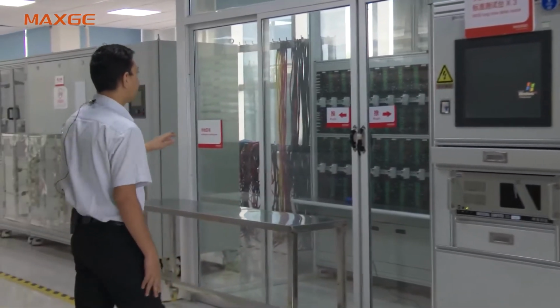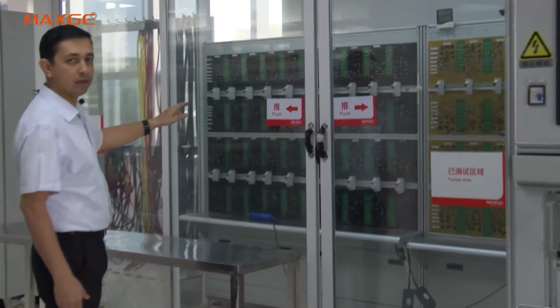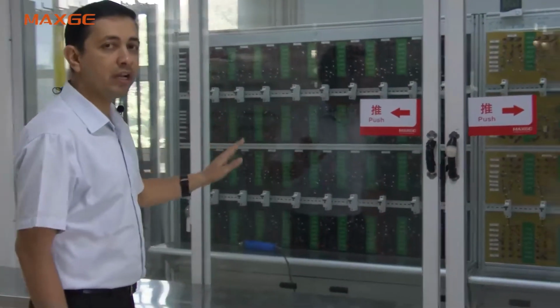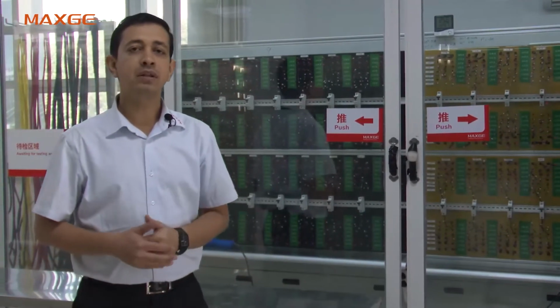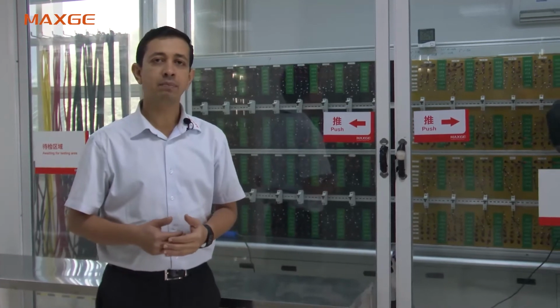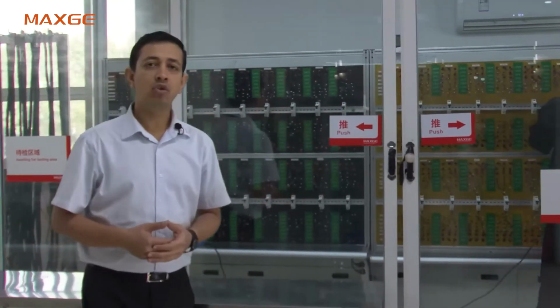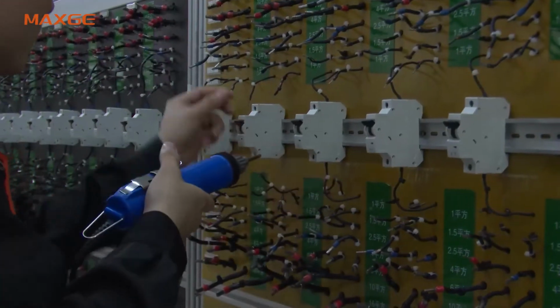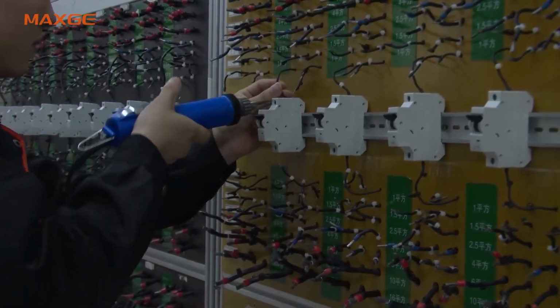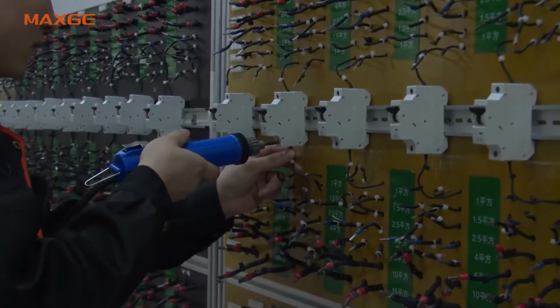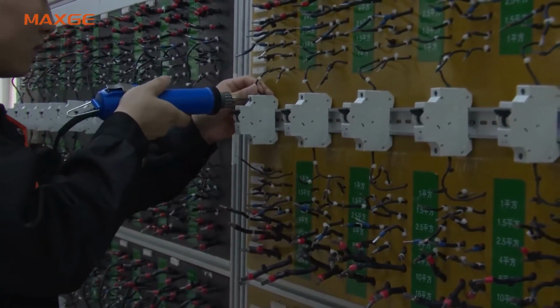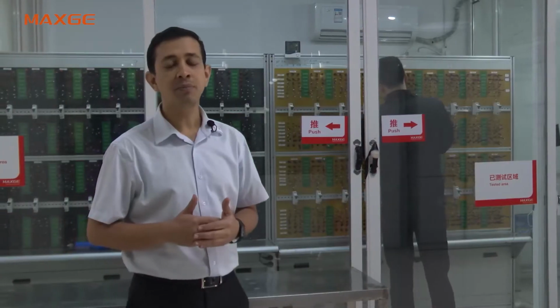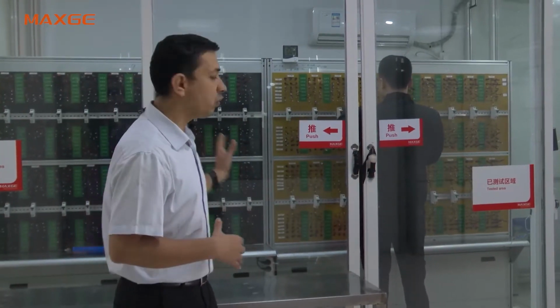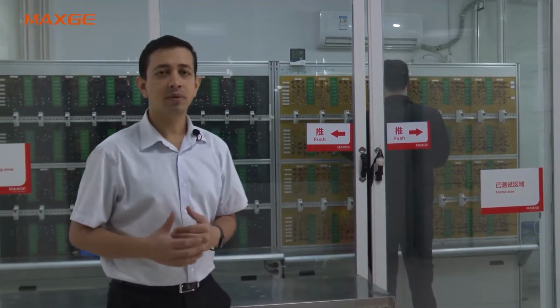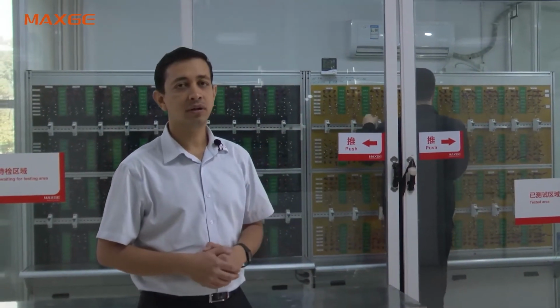So you can come here and see. This long delay test is to check the overload performance of the MCB. So what does it mean? As per IEC 60898 Part 1 standard, the MCB should not trip at 1.13 times the rated current within 1 hour, and the MCB should trip at 1.45 times the rated current within 1 hour. Every MCB should qualify. So for every lot, we take out some sampling pieces and check them here for the long delay test.